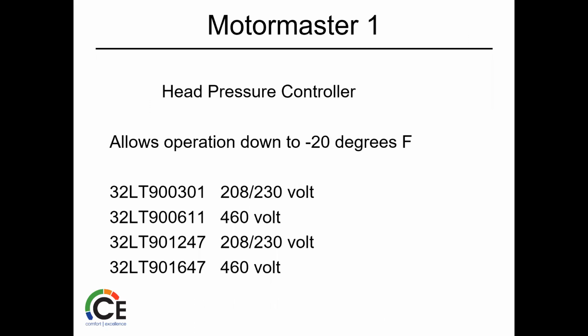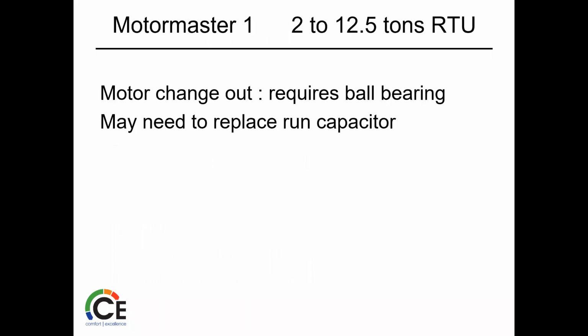So, MotorMaster 1 allows operation down to -20 Fahrenheit. Some of the numbers have changed. The control hasn't, sometimes part numbers change. So you can get that single phase, 208 volt, 460 volt. It just depends on what you're going on. This one does it depending on what type of motor you have, condenser fan motor. We may need to make sure it has a ball bearing motor. And then again, we may need to change the run capacitor. So if you're not sure, that's a great question. Give us a call, give us your model number. Let's see what you're trying to do. We'll help you out.